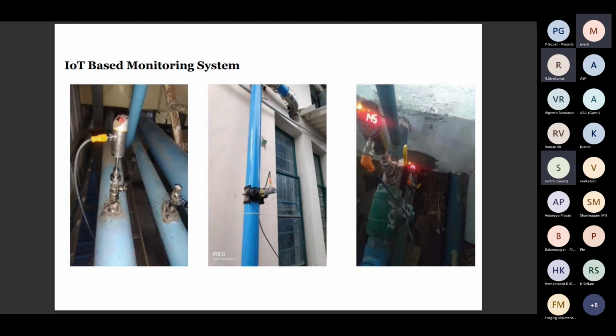Another important feature: if the air compressor has an energy meter, the same energy meter is incorporated into this IoT system. You can quantify how much energy you lose due to air leakage, and what specific energy consumption you develop during the air generation. Every day, every hour, every minute, you can monitor. So this is an excellent kind of system. Whenever I do an energy audit, wherever possible, I use this system. It was obtained through outsourcing, and they have done this extensively, and our energy audit reporting has also been very much enhanced by it.